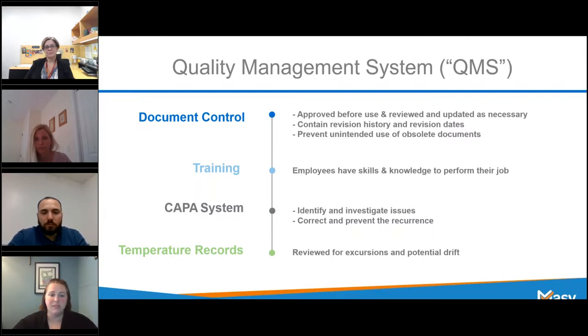It's critical to review the temperature and humidity of the storage chambers. While alarms for out-of-spec conditions require immediate action, reviewing temperature and humidity trends on a regular basis can help you be more proactive in identifying equipment issues before they lead to an excursion. It'll be perfectly normal to see short spikes or dips in your data due to typical day-to-day use of the chamber, such as adding or removing product or preventative maintenance. However, any other anomalies such as a slight drift should be analyzed by your facilities or HVAC team, because this could be an indicator of potential deterioration occurring in the unit. Those slight drifts might not be detectable day-to-day, but if you're reviewing a month's worth of data, they might be more prominent and indicative that additional maintenance is needed.